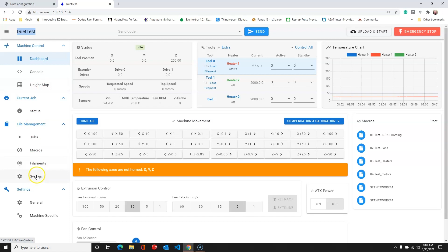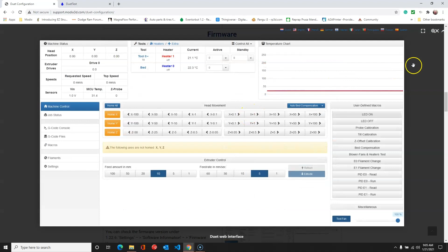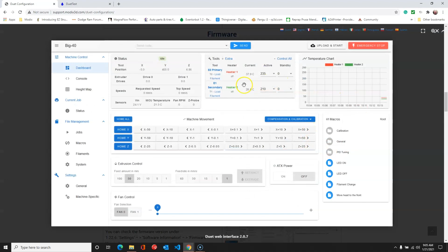If I go back to the Modix online manual, when we come down to the firmware section, it's going to state firmware. There are two versions of the interface: version 1.22, which is this one, and version 2.07, which is this one, and that's the one currently on our machine.